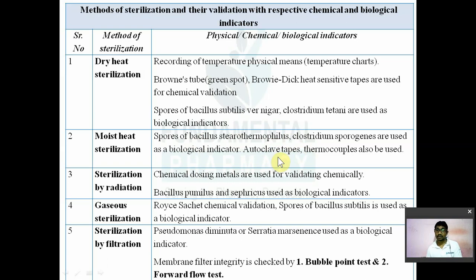Spores of Bacillus stearothermophilus, then Clostridium sporogenes, are used as a biological indicator for moist heat sterilization. Then again chemical indicators like autoclave tapes are available. Then physical methods like thermocouples are also available. Then sterilization by radiation: chemical dosimeters are available for validating chemically.